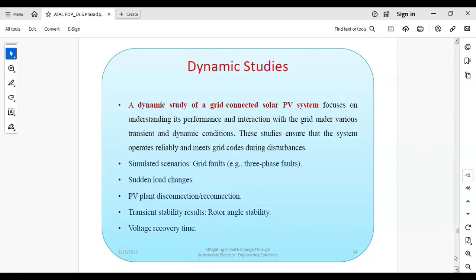Therefore, you have to conduct the transient stability analysis, which is a dynamic study. You have to perform it by simulating the PV plant along with the existing plant. You get the existing plant SLD, prepare the PV plant SLD, make the connection, and then go for the transient stability analysis. That means creating different kinds of faults, like line outages. Suppose a three-phase fault happens on an OHL transmission line at the PV plant end, because the PV plant will be connected to the existing plant through a transmission line. Then what is its effect on the generators at the existing plant?